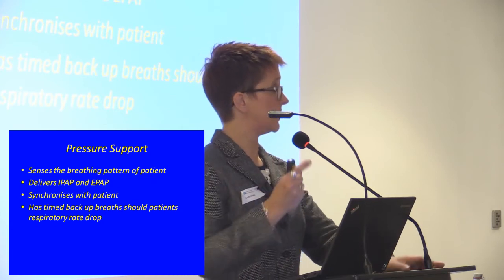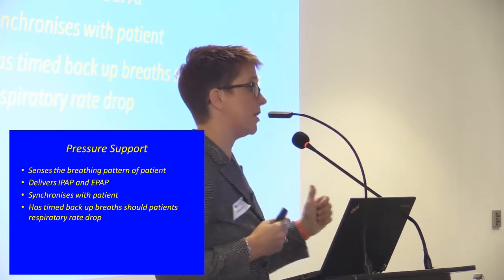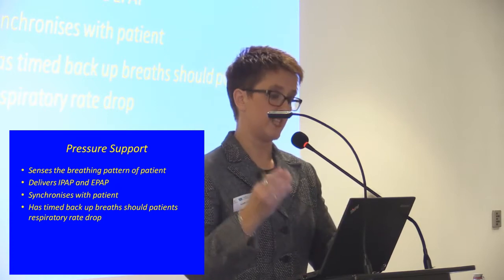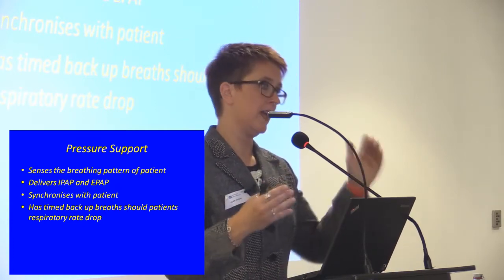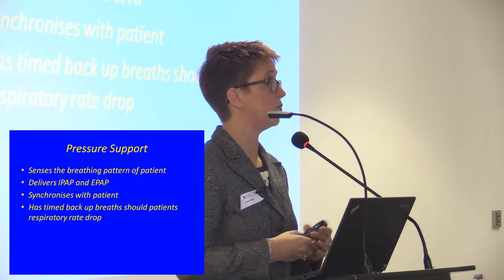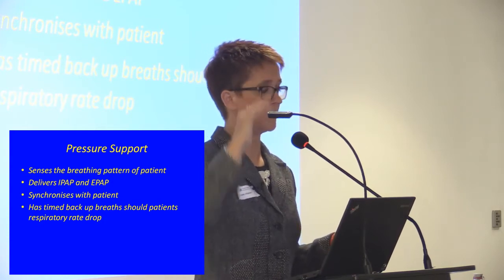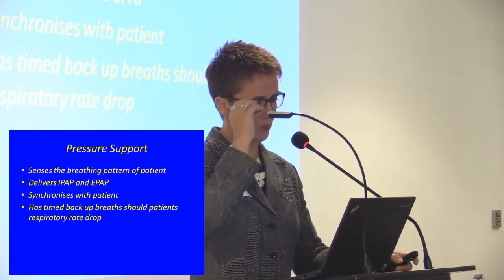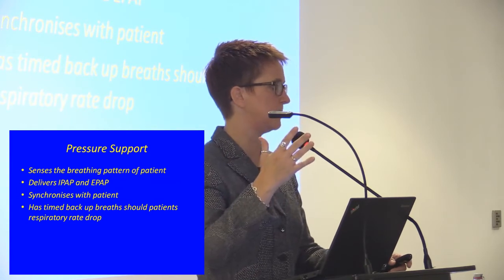Pressure support is probably the easiest one to set up for a majority of patients. We set the IPAP and the EPAP, measured in centimetres of water, because we're giving them pressure above atmospheric pressure, which is 0 centimetres of water. It senses the breathing pattern of the patient.